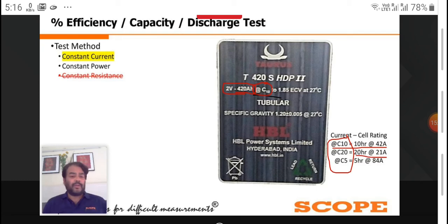So the battery is ultimately getting unnecessarily stressed. If we are talking about the standard, it has to be done with an electronic battery loading unit where you can control the current to the precision. That is what IEEE recommends. What to do if you do not follow it is up to you. We can talk only about what the standard says.